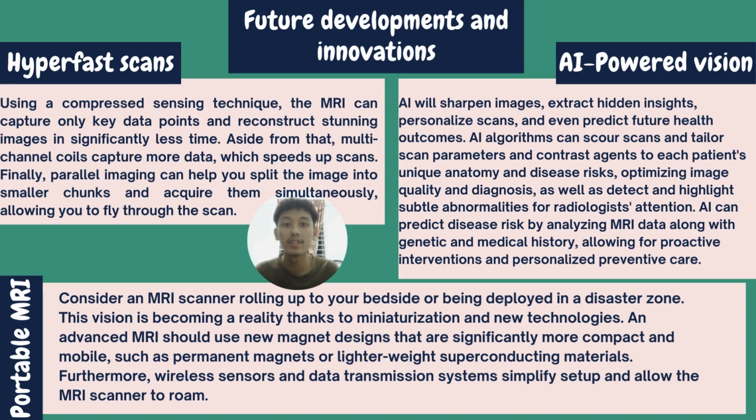So now I'm going to tell you guys about the future development and innovation. The first is hyperfast scans. Using a compressed sensing technique, the MRI can capture only key data points and reconstruct stunning images in significantly less time. Aside from that, multi-channel coils capture more data, which speeds up scans.